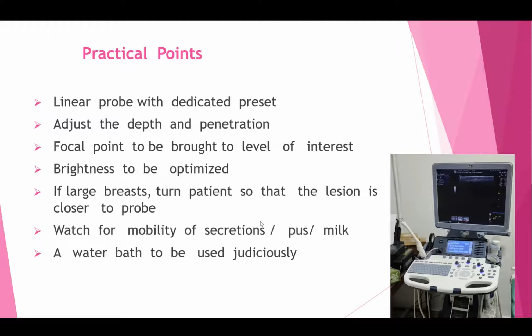Practical points. You have to have a standard Doppler machine. The linear probe with a dedicated breast preset is to be preferred. You sit with your application specialist and form a dedicated preset for that. Adjust the depth and penetration. The focal point is to be brought to the level of interest for maximum information. Brightness is to be optimized. If large breasts, then turn the patient so that the lesion is closer to the probe. Watch for mobility of secretion, pus or milk, which occurs within a cystic cavity, abscess, or within the ducts. A water bath is to be used judiciously. This is also called the standoff pad.